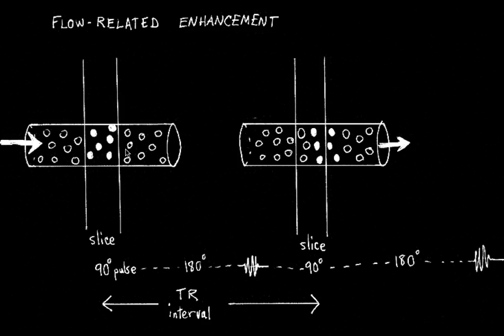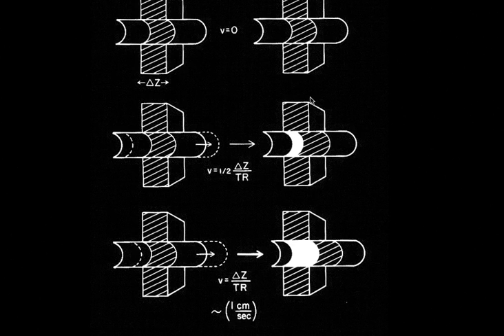Here's an example. Nuclei are flowing in, and if we give a 90-degree pulse on the slice plane, we saturate the nuclei in that slice. After a TR interval, some of those saturated nuclei have flowed out of the voxel, and new unsaturated nuclei have flowed in. When we give another 90-degree pulse, we will have many unsaturated nuclei, and therefore we get much higher signal intensity from these nuclei than from those next to them. This is flow-related enhancement.